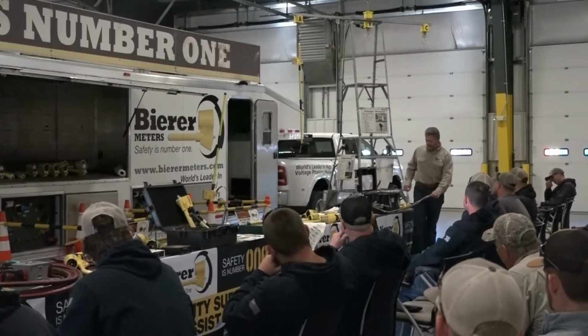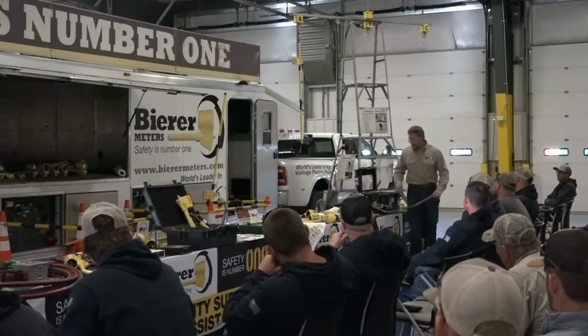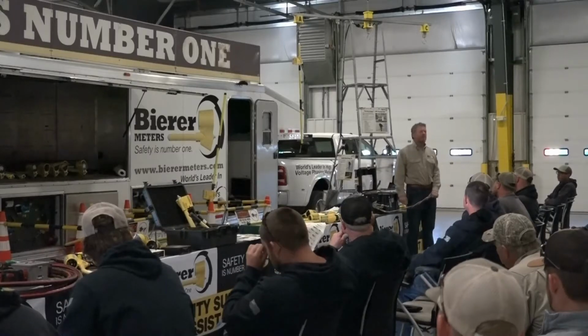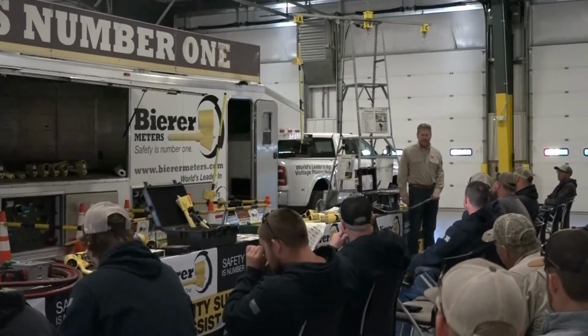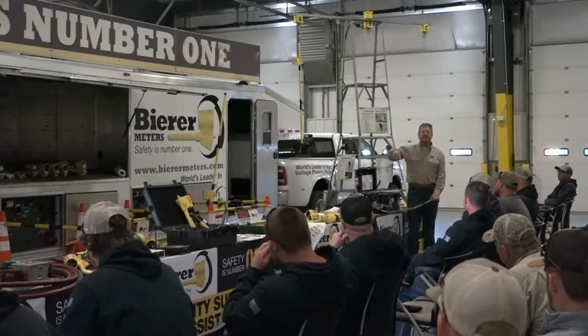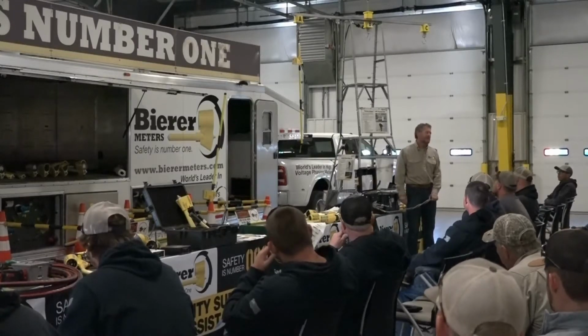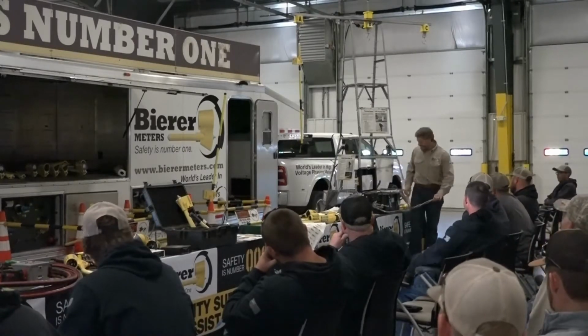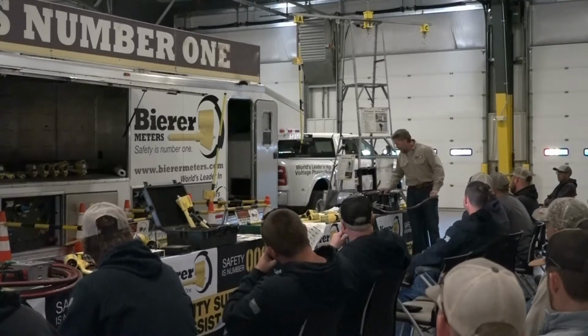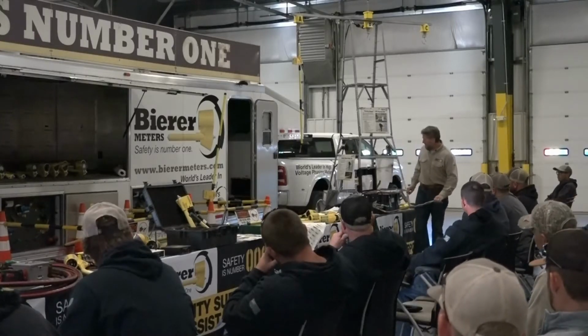This is a number 2 cable. We suggest a 1-aught or a 2-aught because they're stiffer. Cables that are flimsy will snap over time easier, and the strands can break more easily. A number 2 requires 165 amps.